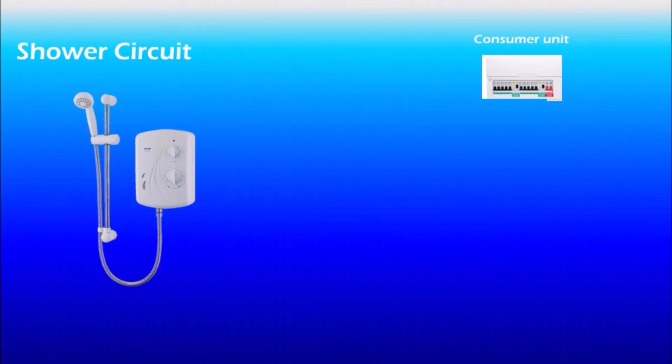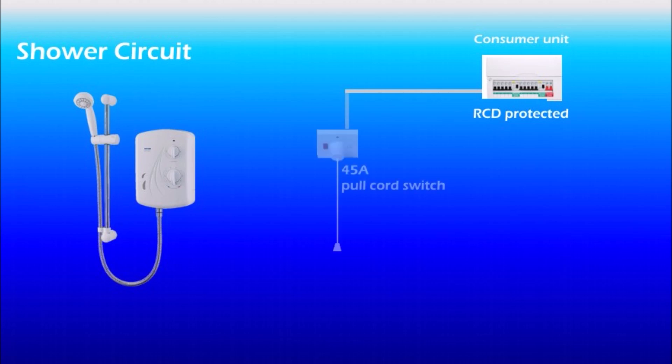The next circuit that you might have at your home is a circuit for the shower unit. This also has to be dedicated circuit and RCD protected, as the cable runs under the shower. So we run the cable from consumer unit to the pull cord switch that is located on the ceiling of the bathroom. If you don't like the pull cord switches you can have wall mounted 45 amp switch but this has to be somewhere outside the bathroom.